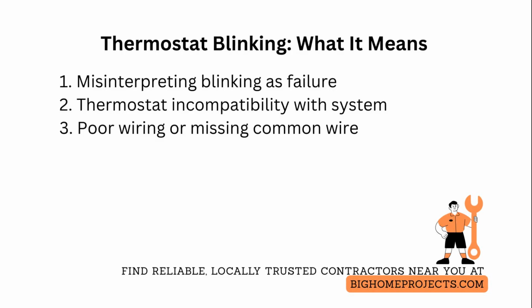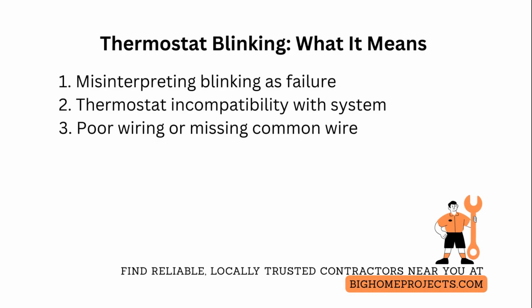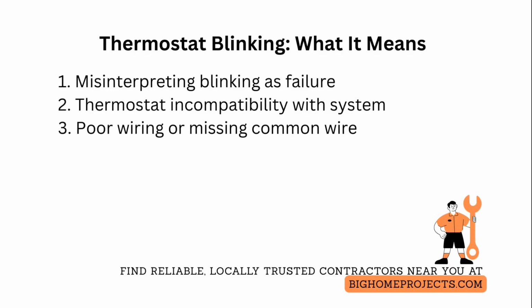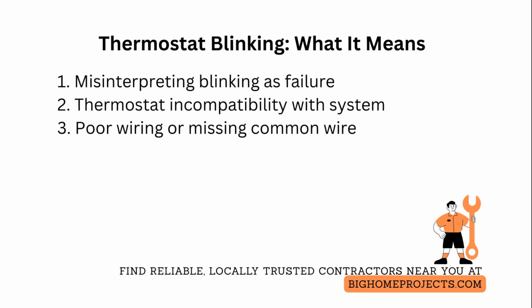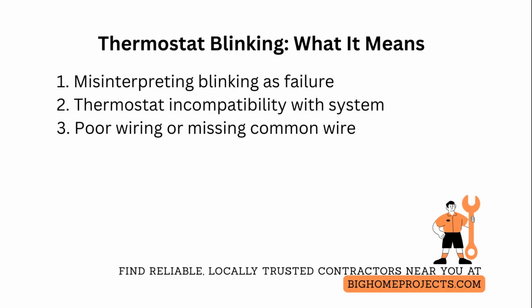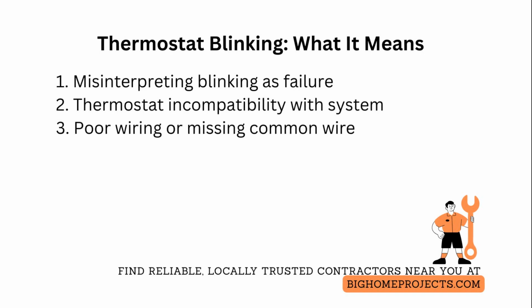The third frequent problem is poor wiring or a missing common wire, leading to intermittent resets and blinking. Remedy by verifying a solid common wire connection to the new thermostat, or installing a common power adapter or new transformer, and measuring steady 24-volt output before finishing installation.